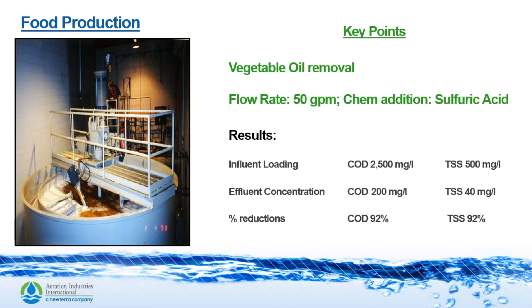Now I would like to go through a few installations of the microfloat unit. In this example, we have a food production plant that was removing vegetable oil from their processed water. The flow rate was 50 gallons a minute and they added sulfuric acid for pH adjustment. The influent loading was COD of 2,500 mg/L and TSS of 500 mg/L. The effluent concentrations were 200 mg/L COD and 40 mg/L TSS, equating to 92% removal of both COD and TSS.